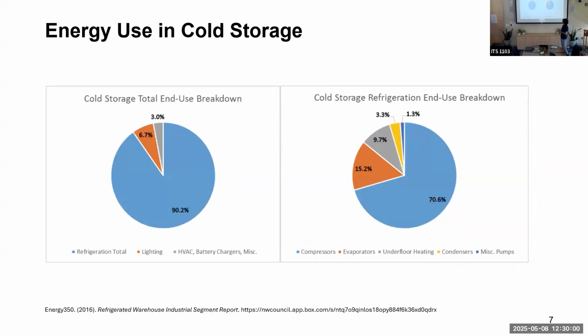In a cold storage facility, the majority of the demand is in the refrigeration equipment. So 90% of all the electricity gets used in the refrigeration plant. And if you break down that refrigeration end use, most of it is in the refrigeration compressors, which are actually doing the cooling. The next biggest thing is your evaporator fans, which are cooling the facility. So if you want to explore load flexibility in cold storage facilities, our biggest opportunity is within the cooling system itself. There are some other opportunities with forklift charging stations, timing defrost, or exploring more efficient ways of underfloor heating, but by far the biggest opportunity is within the cooling system itself.